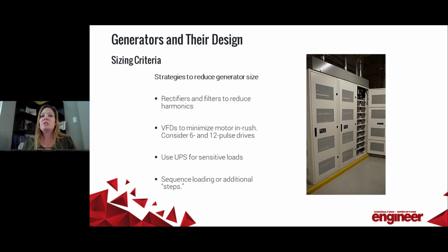So ultimately, our job as engineers is to provide a generator system that will support the loads, but also fall within the client's budget. So once we've assessed all the sizing criteria, most of which indicated that a good solution could be to increase the alternator size, we also then need to consider ways that we can reduce the generator size and still meet the criteria. After all, a properly sized generator is not going to be oversized as well. It's going to save the owner money, not only in upfront costs, but on any cost that might be needed for monthly load banks if you don't have enough load connected to the system to support the required testing.